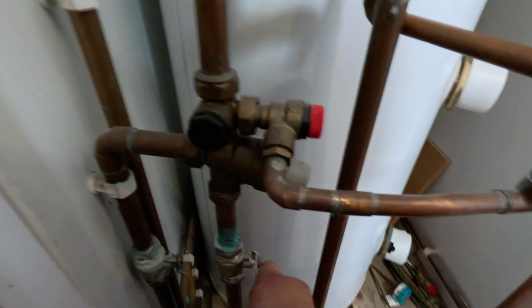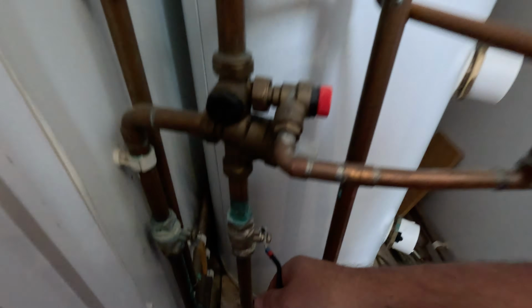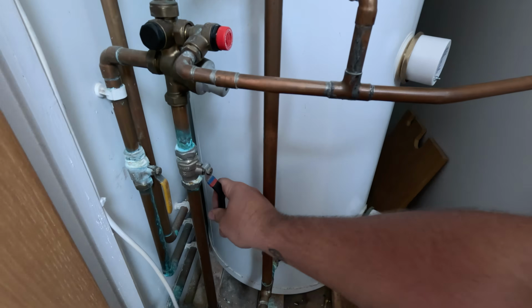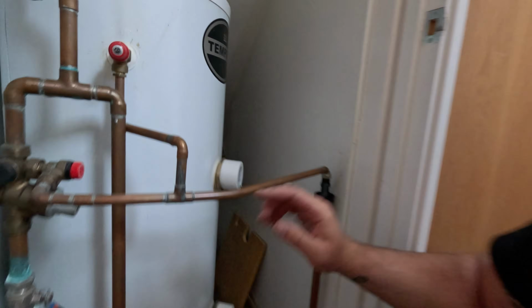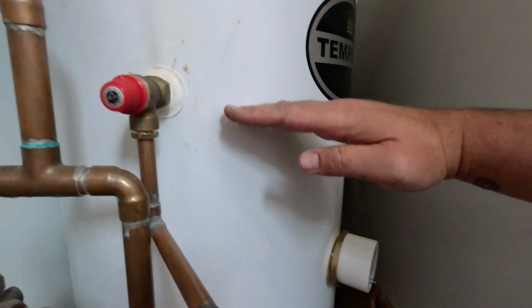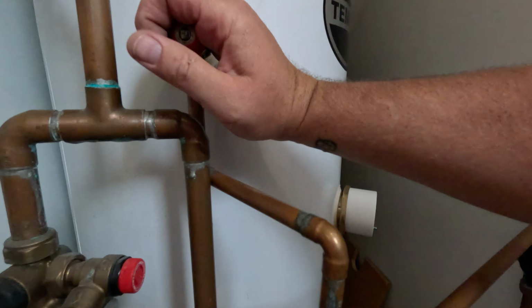With that connected up, let's get the water back on. Make sure that's off. Let's get the water back on, pressurise it back up and see if it's all right. So with that tank filling up now, if we open this T&P valve, obviously as the water rises up, as soon as it gets to this point, it will start coming out and then we know we are above that new immersion and stat. So we know that that is all good. Looks okay at the minute.